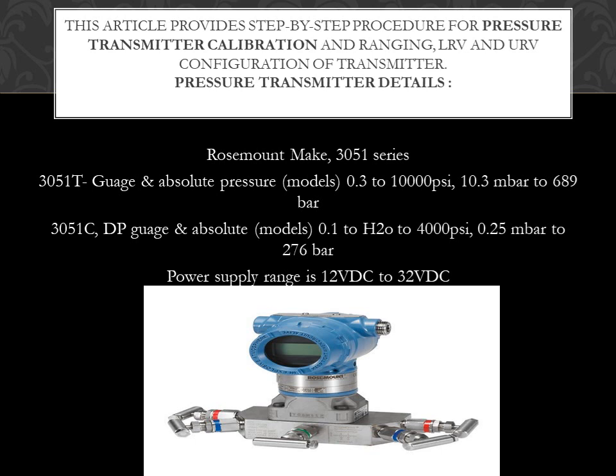We are taking the Rosemount 3051 series. 3051T gauge and absolute pressure model, 0.3 to 10000 psi, 10.3 mbar to 689 bar. 3051C DP gauge and absolute model, 0.1 to H2O to 4000 psi, 0.25 mbar to 276 bar. Power supply 12 volt to 32 volt DC.